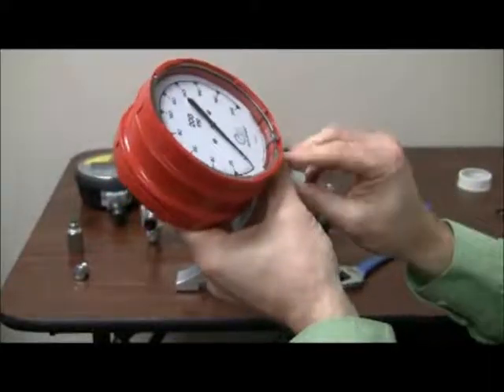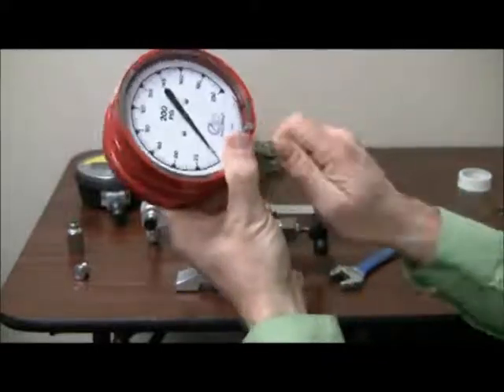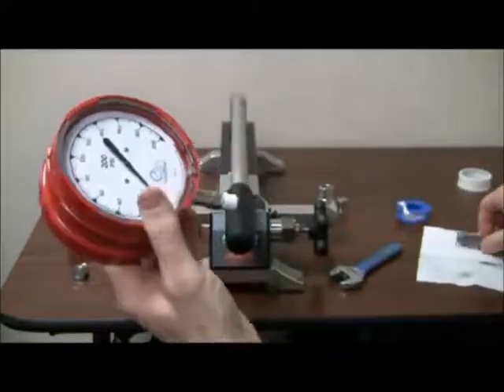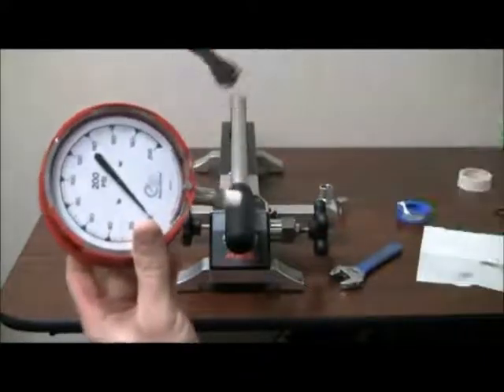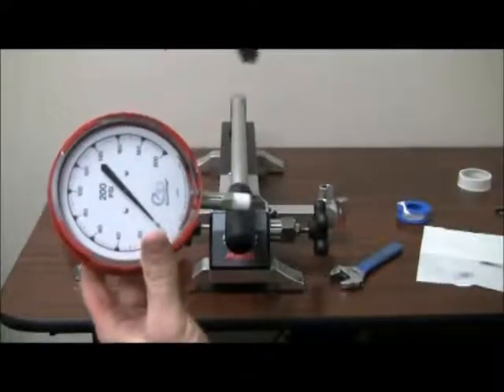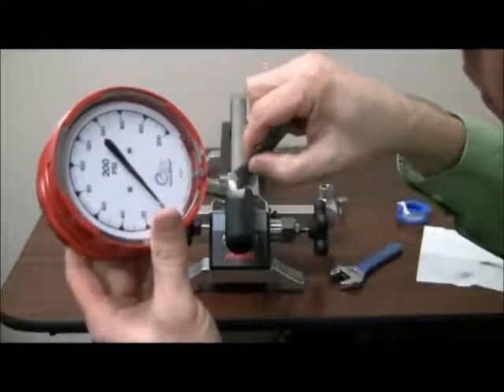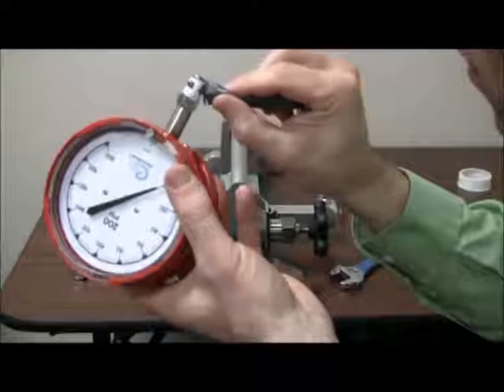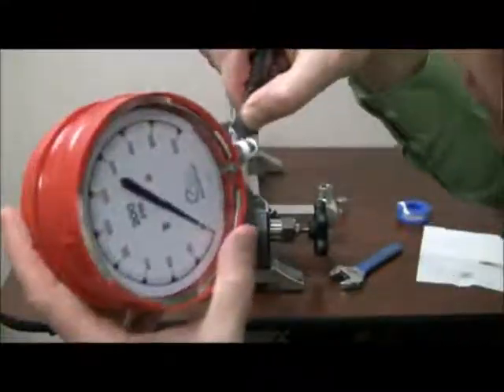Now that we have an evenly coated gauge, we're going to apply some anti-seize lubricant gently around the gauge itself. A thin coating of anti-seize lubricant over the Teflon tape prevents extrusion of the Teflon tape as the threads mate. This is very important when using stainless on stainless.